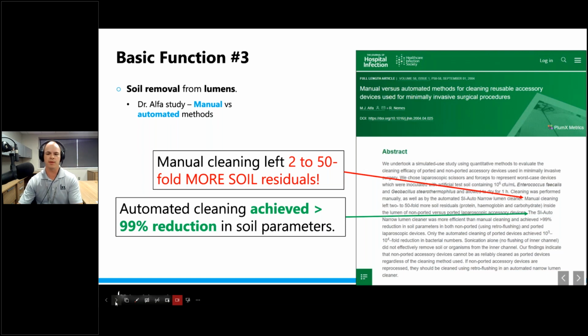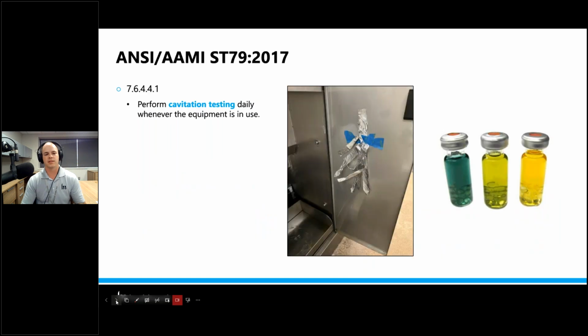All right. So what does that mean exactly? Well, one way to test for cavitation is to actually use aluminum foil. All right. Aluminum foil should dimple as it is exposed to cavitation. The problem with using aluminum foil, hopefully it's already kind of obvious to you before I even say it, but performing a cavitation test in your ultrasonic cleaner with aluminum foil on a daily basis, with all the variation involved, where are we going to put it in the tank? How are we going to run the cycle? How are we going to determine if it's a pass or fail result? There's some subjectivity to that. That is one of the methods that could be used, but in the real world, it would be very difficult to actually perform that test and then understand and determine the results of it.